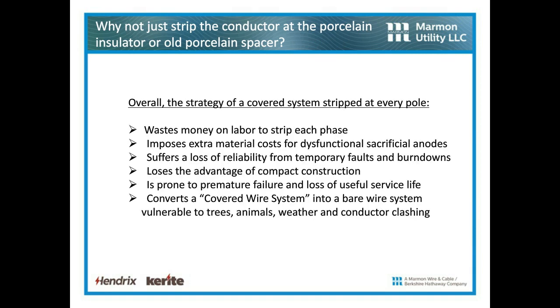So the strategy of a covered conductor stripped at every pole wastes money on labor, imposes extra material costs for dysfunctional sacrificial anodes, suffers a loss of reliability from temporary faults and burn down, loses the advantage of compact construction, is prone to premature failure and loss of useful service life, and essentially converts a covered wire system into a bare wire system.